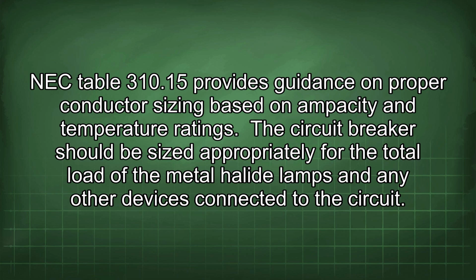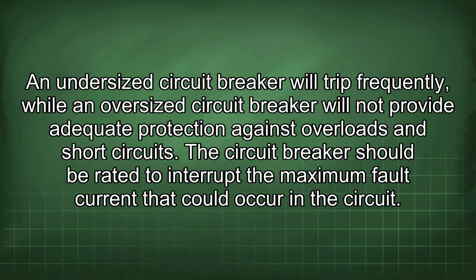The circuit breaker should be sized appropriately for the total load of the metal halide lamps and any other devices connected to the circuit. An undersized circuit breaker will trip frequently, while an oversized circuit breaker will not provide adequate protection against overloads and short circuits. The circuit breaker should be rated to interrupt the maximum fault current that could occur in the circuit.